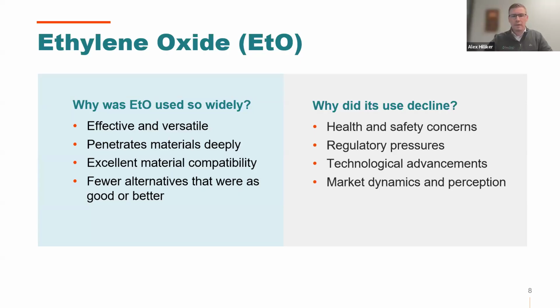The challenge with ethylene oxide is that it takes a really long time to aerate and off gas. That's because of that ability that it has to penetrate very deeply into the product. So it takes a long time for it to come back out, which can cause well-documented health impacts. So ethylene oxide is a known human carcinogen. It causes lymphoid and breast cancers. It's a mutagen and a teratogen. It can cause birth defects and miscarriages if you're overexposed.